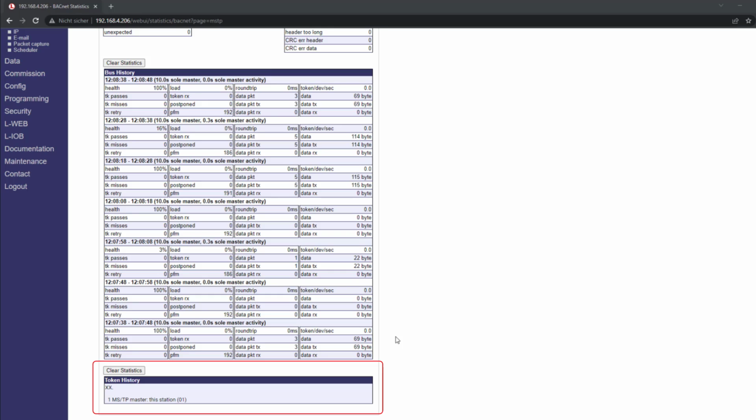As a conclusion, we can see that either some network parameters are not set up correctly, therefore I'd recommend verifying the uniqueness of the node ID and the correct setting of the baud rate, or if that has been already checked and the communication is still not working, then as a next step, check the wiring and make sure it is cabled as recommended earlier.